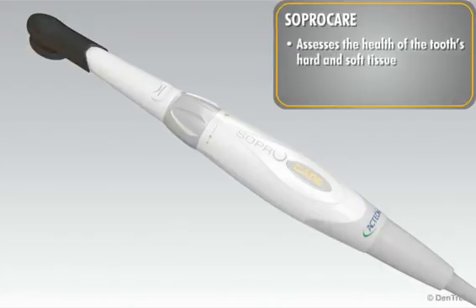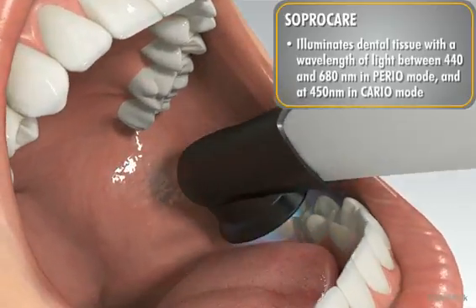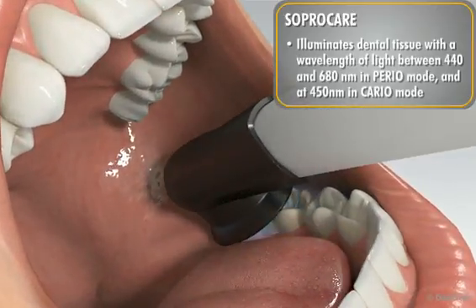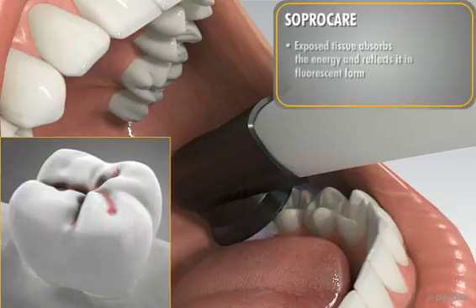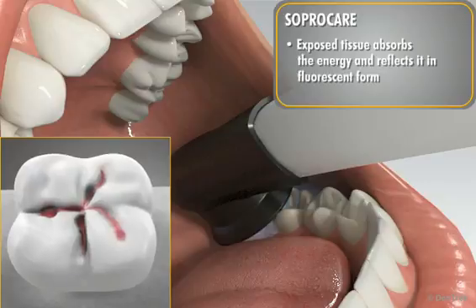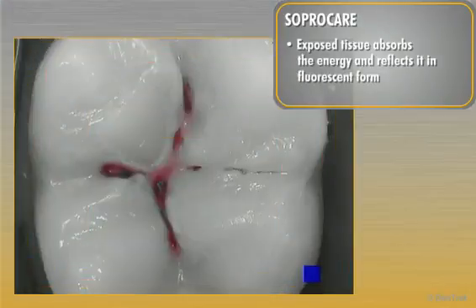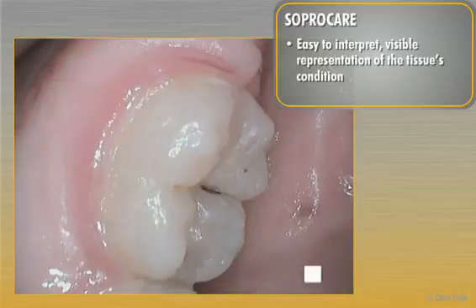SOPROCare assesses the health of the tooth's hard tissue as well as the soft tissue that surrounds it. It illuminates dental tissue with a specific wavelength of light between 440 and 680 nanometers in perio mode, and at 450 nanometers in cario mode. The exposed tissue absorbs the energy and reflects it in fluorescent form. Images obtained through fluorescence analysis are superimposed over the anatomic images, creating an easy-to-interpret and visible representation of the tissue's condition, which is otherwise invisible under white light.